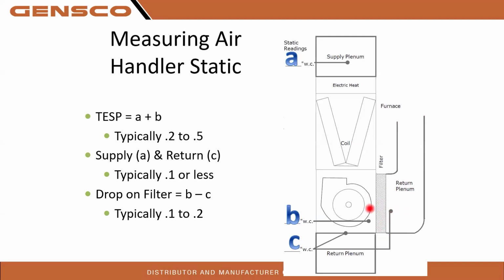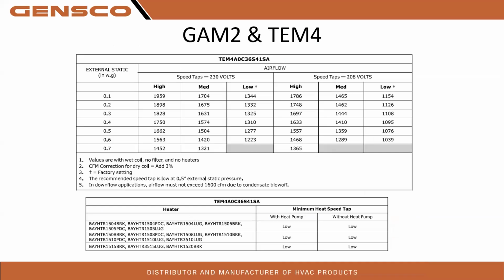But if you're taking your static pressure and you're getting a 0.6, 0.7, you know something's up with that return. So again, it's all about eliminating questions and concerns. If you can pinpoint a high static area, you know where to address your static pressure. GAM2, TEM4s, you don't see too much of these. They're still there. I mean, there's a lot in the field, but not on new construction.